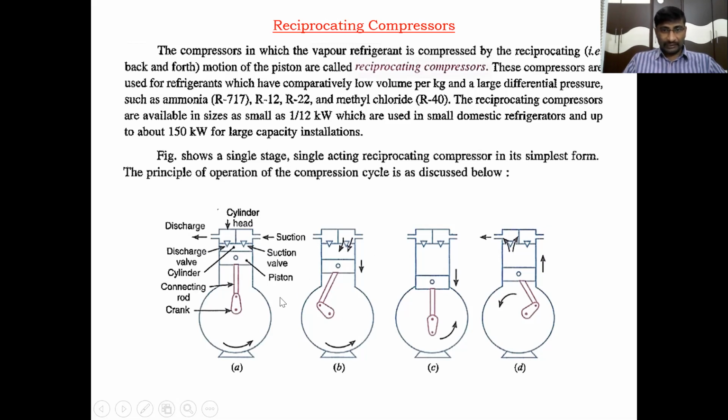These are the figures. During the suction stroke, the piston moves towards the BDC from TDC. This is the suction stroke. When the suction stroke starts, the suction valve opens. The refrigerant coming from the evaporator will enter the cylinder. After entering the cylinder, when the piston is at the bottom dead center, the two valves are in closed position due to the pressure difference on either side of the valves.